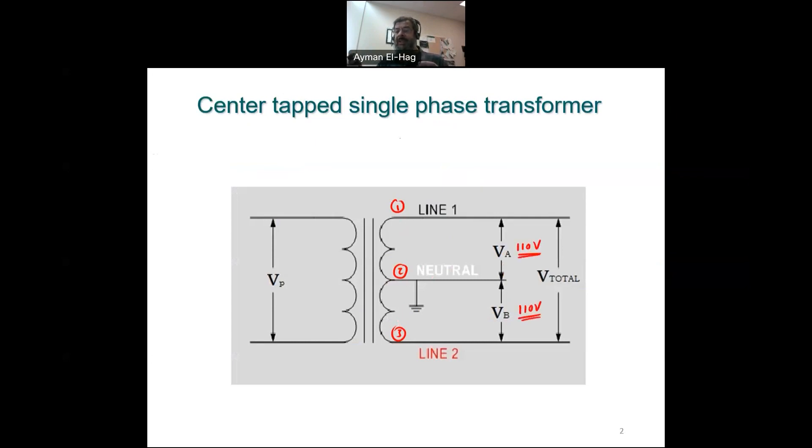The question is why we need this center tap. Why don't we have just a single phase transformer with the output is just 110 volt? Because between line one and line two now you will have 220 volt. So now this single phase transformer gives you the option of two voltage levels: 110 and 220 volt.